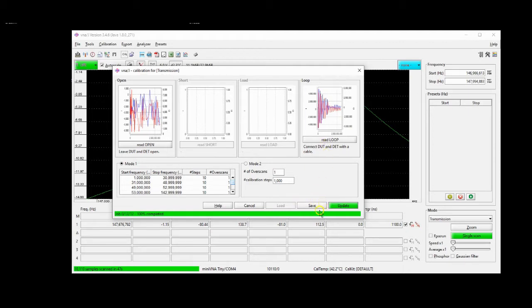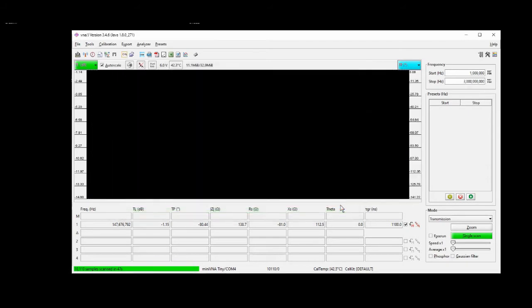And as I stated before, I could save this calibration data here for later use, so I don't have to sit around and watch it do its thing. But we're going to update, which sends this calibration data to our software. And now we set our start and stop frequencies, which is 144 MHz to 148 MHz. Now we connect our cables up to the attenuator so that we can see what its performance is across the entire 2-meter band. We're now connected. We're not interested in the phase shifts, so we're just going to shut that off. All we're interested in is transmission loss, because all we're doing is measuring the gain of this amplifier. So we'll do a single scan.